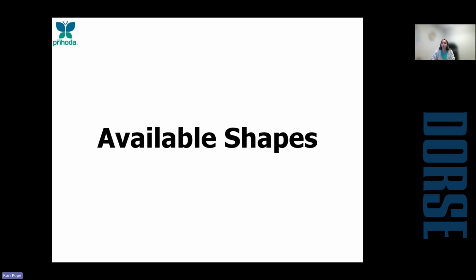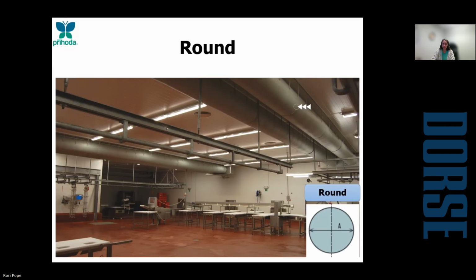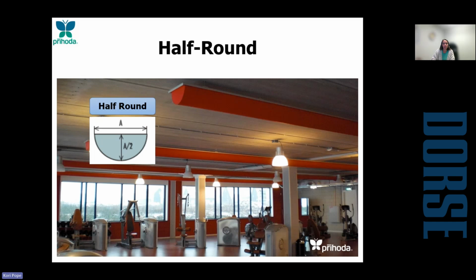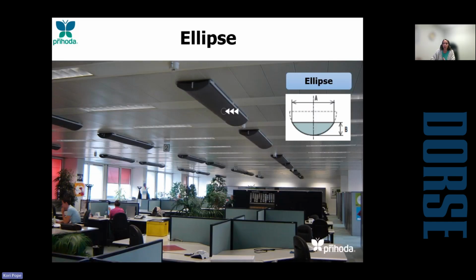So the other fully customizable option with fabric duct is the actual shape of the diffuser itself. So round is what most people traditionally associate with fabric duct. However, we have it in half round as well as in ellipse. So both half round and ellipse can be suspended or flush mounted to the ceiling, so these are more ideal for your lower ceiling spaces. The ellipse just has a smaller aspect ratio when compared to the half round.